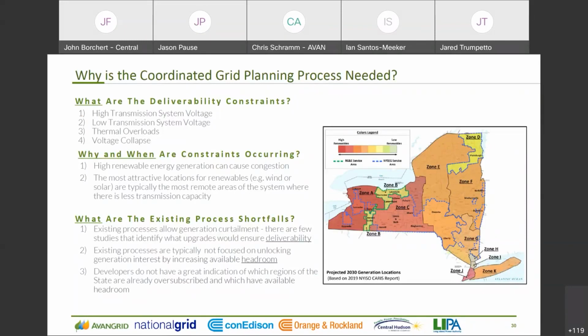Typically, the most attractive locations for renewables are the most remote and weakest areas of the system, where there's a lot less transmission capacity. This high amount of generation can cause congestion resulting in thermal overloads, but can also cause high voltage, low voltage, and in extreme cases voltage collapse.